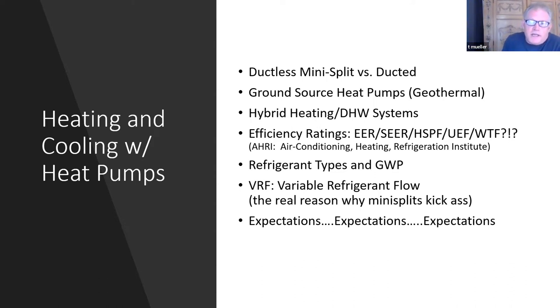A heat pump is different in that you really don't want to over-design it. You want it to be at the limit, so it's running at capacity on the worst case scenario day. Back to our climate zone, we're a heating climate zone, so on the coldest day of the year you want your heat pump working at capacity, maybe even slightly beyond its capacity, so that for 95% of the days of the year you're completely covered, and that way you're ensuring maximum efficiency.